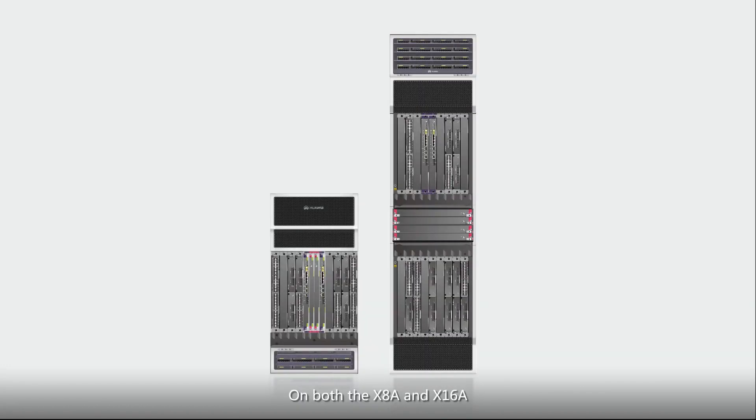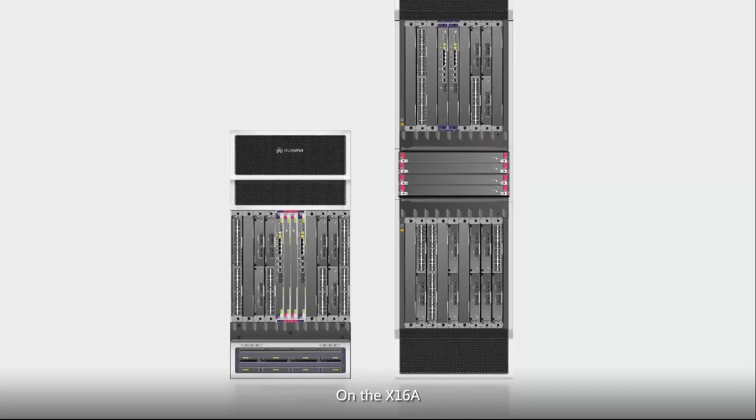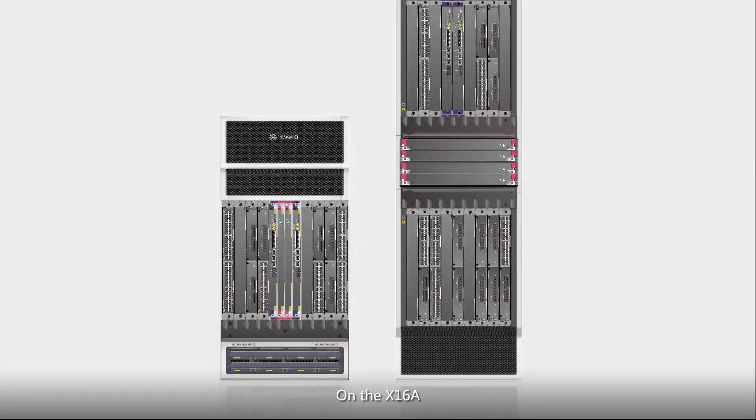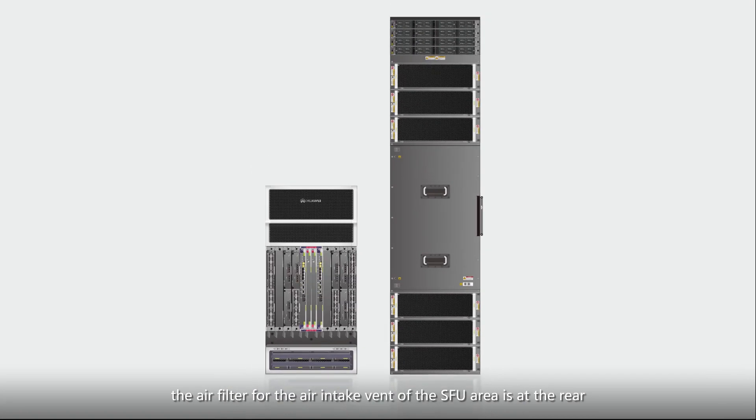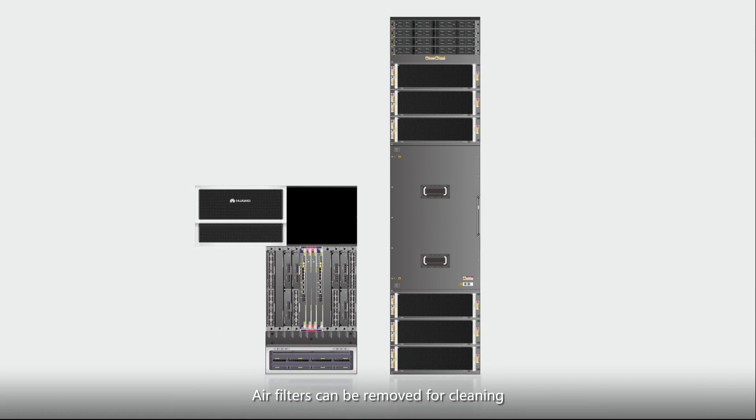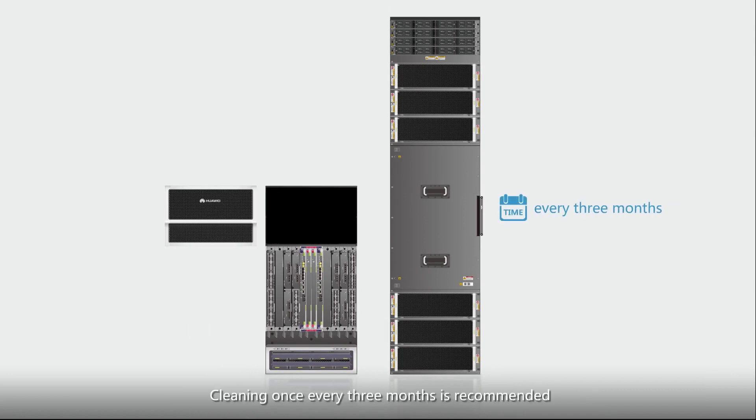On both the X8A and X16A, air intake vents are configured with air filters. On the X16A, the air filter for the air intake vent of the SFU area is at the rear. Air filters can be removed for cleaning. Cleaning once every three months is recommended.